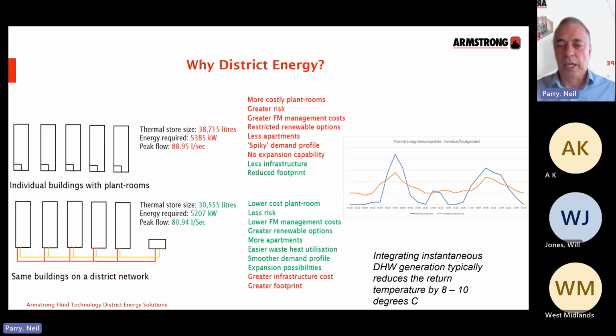So why district energy? Well, what I've done first of all is a very quick calculation on the left-hand side of this slide, where we're looking at 5 individual buildings with 5 individual plant rooms. If you add up all those plant rooms, you find that the calculation tells you you need 38,715 litres of thermal storage, 5,385 kilowatts of energy, and a peak flow of 88.95 litres per second. If you connect those same 5 buildings to a centralized, or rather decentralized, energy center, then because you're adding them together, you get diversification of load, and you can see from the calculations that everything is a little bit smaller. So smaller thermal store, lower amount of energy required, and a smaller peak flow rate to do the same loading. So that's really one of the benefits.